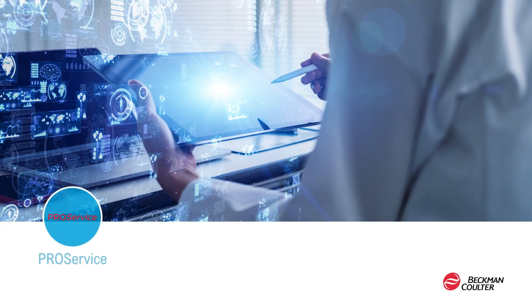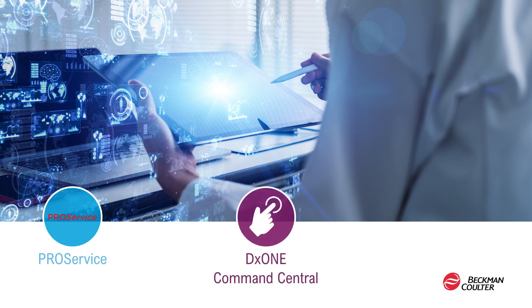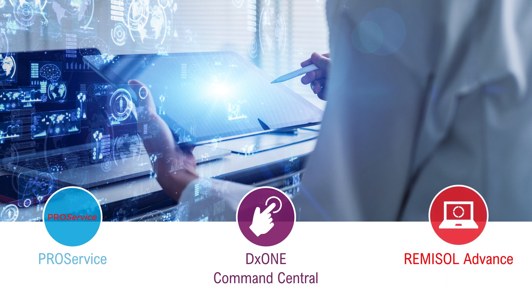Labs now have the option to connect the DXU Iris with our advanced software solutions to take command of their lab. The ProService remote service tool helps labs be more productive as it identifies potential issues before they impact the workflow, automatically notifying service and support staff to resolve instrument issues without the need to wait for a service visit. High-volume labs will find that the convenient DxONE Command Central remote monitoring empowers one user to manage multiple Beckman-Coulter instruments in real time, all from a single workstation. REMISOL Advance, our middleware solution, provides efficiency within and across the laboratory network through process automation and standardization.